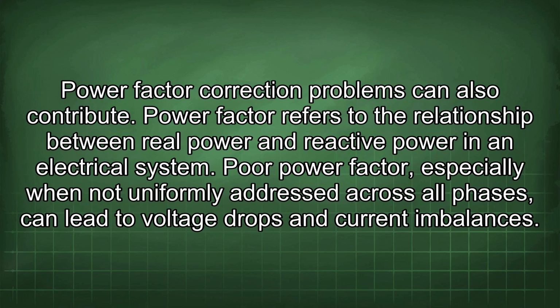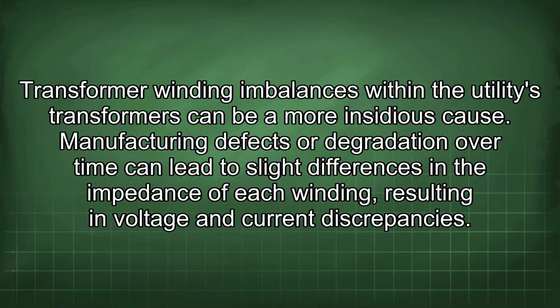Power factor correction problems can also contribute. Power factor refers to the relationship between real power and reactive power in an electrical system. Poor power factor, especially when not uniformly addressed across all phases, can lead to voltage drops and current imbalances. Transformer winding imbalances within the utility's transformers can be a more insidious cause. Manufacturing defects or degradation over time can lead to slight differences in the impedance of each winding, resulting in voltage and current discrepancies.